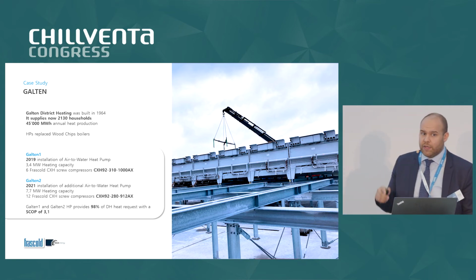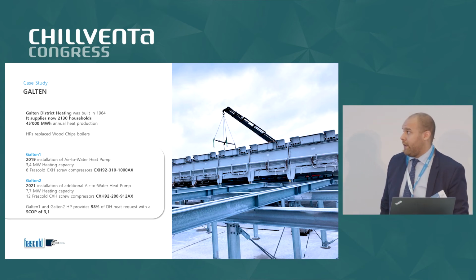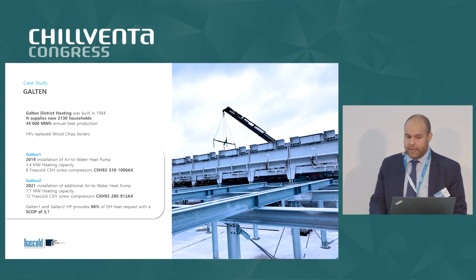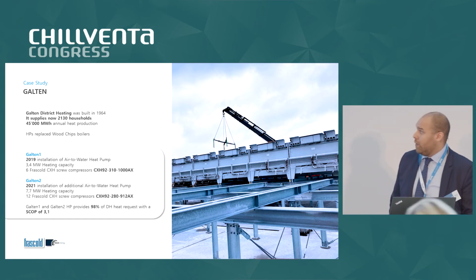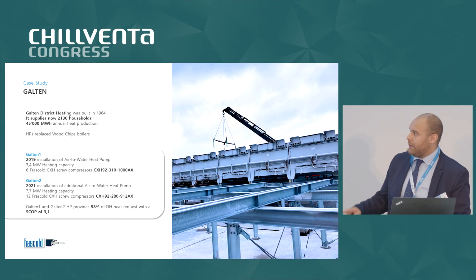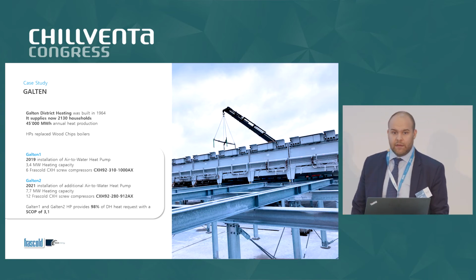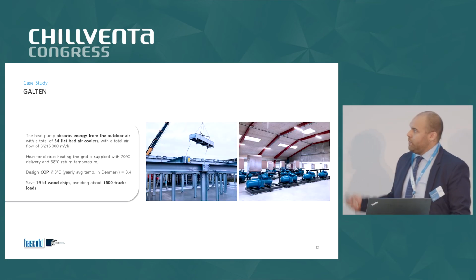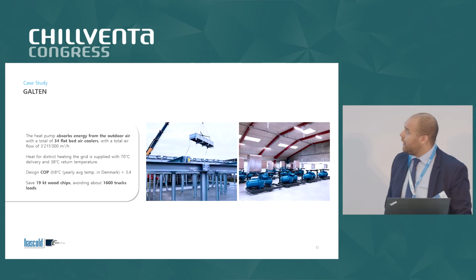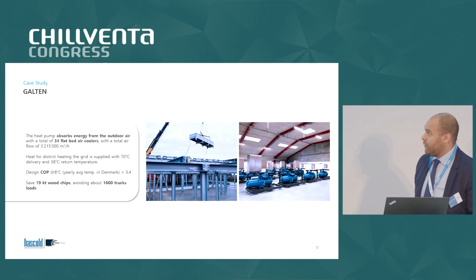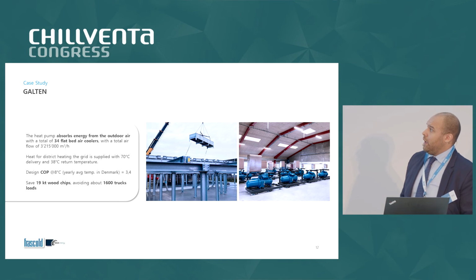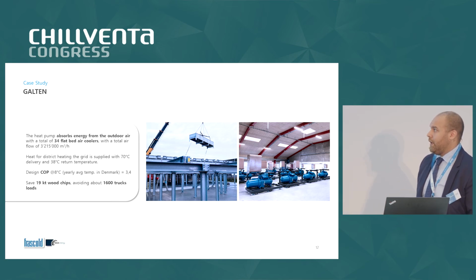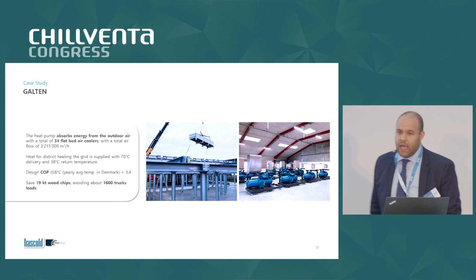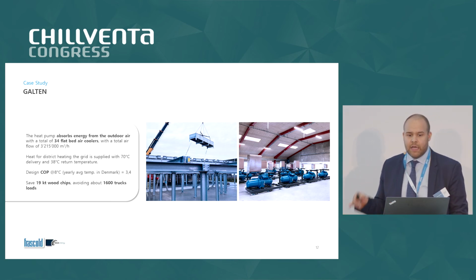Then, after 2 years, in 2021, they installed an additional heat pump with a heating capacity of 7.7 megawatt, with 12 additional CXH screw compressors, ATEX certified. And now this system, Galten 1 and Galten 2 combined, provides basically all the heat requests of the community of Galten. You can see some other specifications about the evaporator, 34 flatbed air coolers. The designed delivery water is up to 70 Celsius, and the design COP in the average condition in Denmark is 3.4.